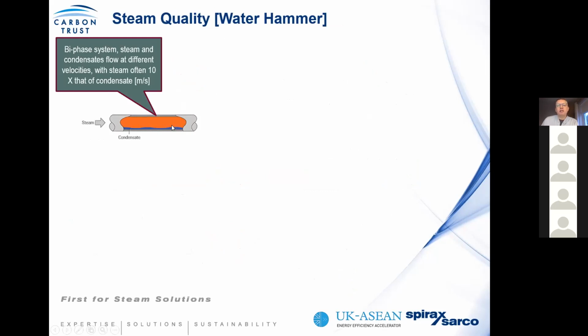So let's explain a bit more about water hammer, because again, this is a common problem with steam distribution systems. So if you take your steam distribution header, again, please understand that it's not just steam vapor, because a steam system by design will lose heat unless you control against it. And the heat loss is determined by how effective the insulation is or the design of the system. However, what you will find is that in your steam system, you have a biphase system, which is a mixture of steam and condensate. However, what you will find is that the end user will determine the velocity of steam. So the water velocity, or the motion of condensate at the base of the pipe, does not travel at the same velocity as that of steam. And sometimes the steam velocity can be 10 times greater than that of the condensate flowing through the pipe.